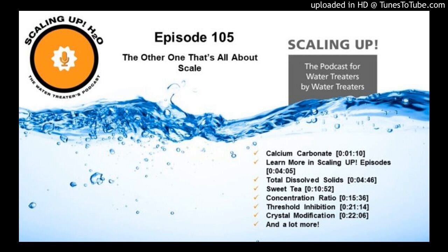Okay, well, we all know what the concentration ratio is. If I concentrate something up 6 times, then my concentration ratio is 6. Well, the reciprocal is just a big fancy word that means I'm going to create a fraction by putting 1 over 6. And then whatever my makeup is, I'm going to multiply it out by 1/6.